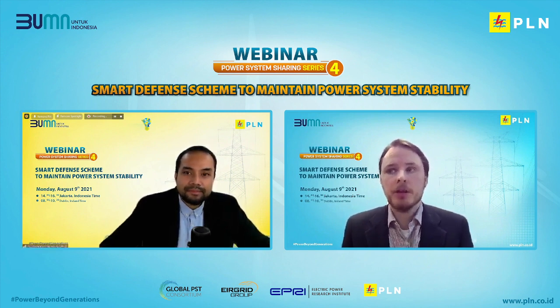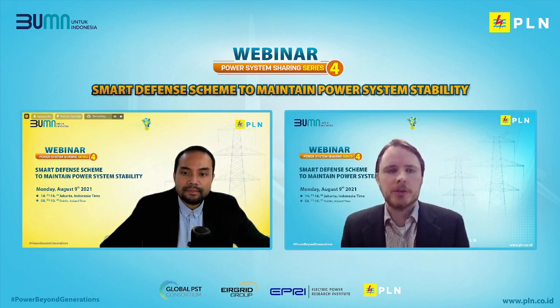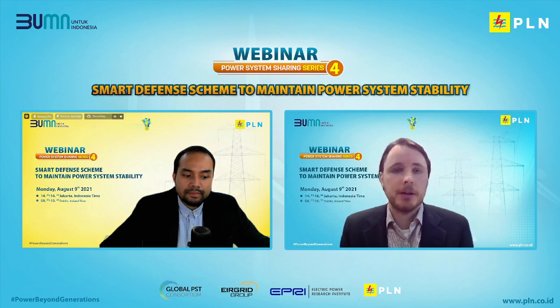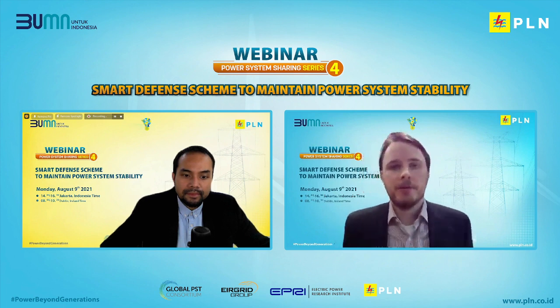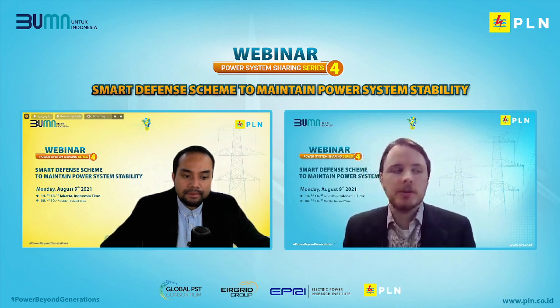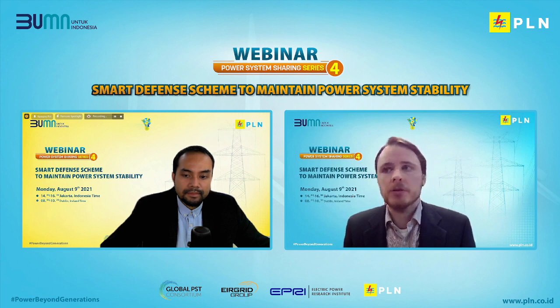No, just to mention that in South Australia, they have a large battery bank. I think it's about 100 megawatts, and that has been used quite extensively to mitigate frequency disturbances very quickly. And indeed, it has responded to overloads on the interconnector between South Australia and the main Australian grid for exactly that scenario. And it responds within 100 milliseconds. So if very fast response is necessary, there are those types of solutions as well.